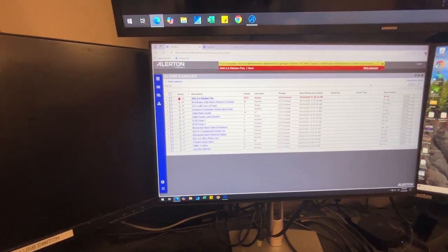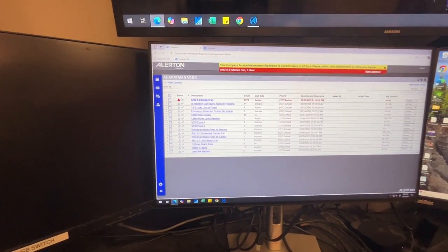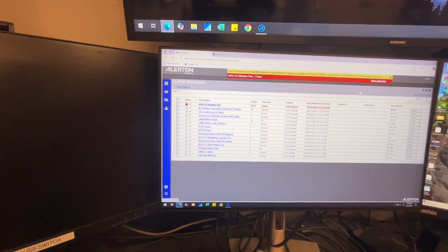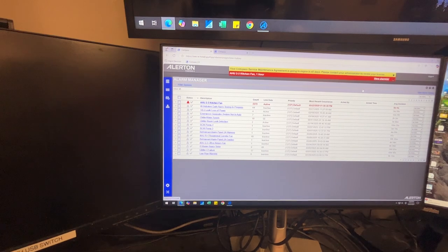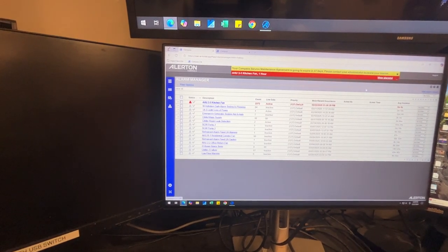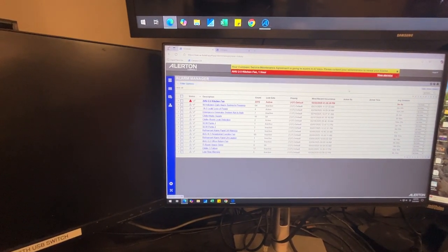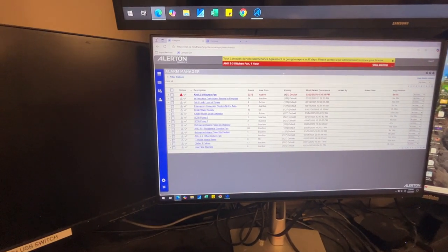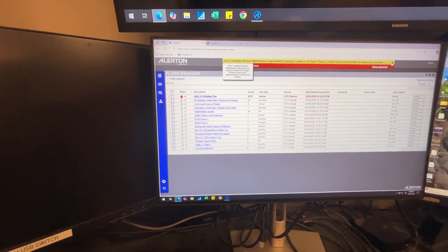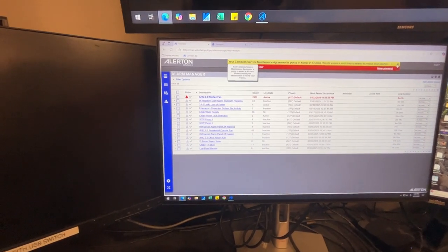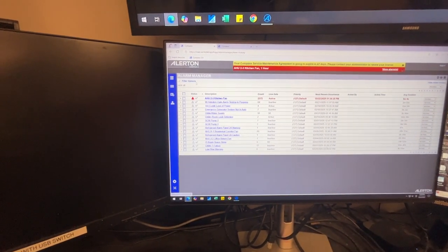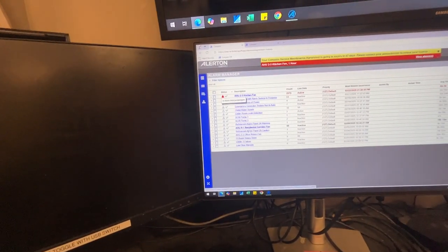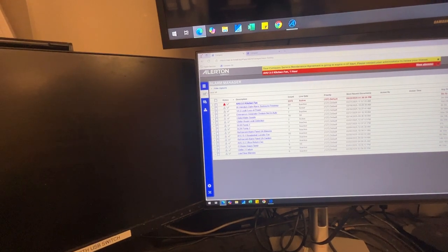I believe because it's ramping down with a VFD, I think that the CT, which provides you, it's detecting whether the motor is on or off based on amperage being pulled through one of the legs. I think because we ramp down the power with a VFD, the calibration is off, and now it will start, stop, every time the fan is on and off. So Climatech was working on this, but that one is still an issue.